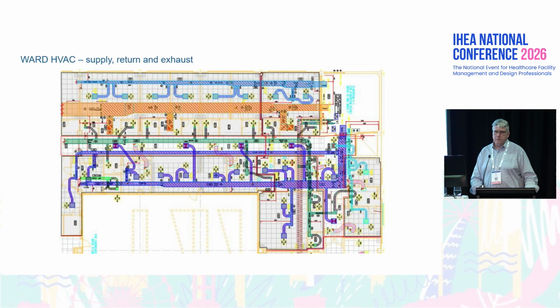When we look at how air gets from the air handling unit into the wards, we have a very complex mix of ductwork, generally a lot of it fixed, but also flexible ductwork feeding out through the air supply registers. This is stuff we should all know about, but when chasing a mould issue, it can be problematic identifying the source. Often you need to start at one point, generally the air handling unit, and work your way out to find where the challenges are.